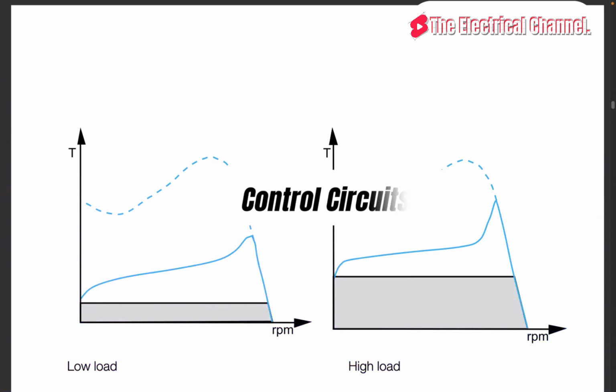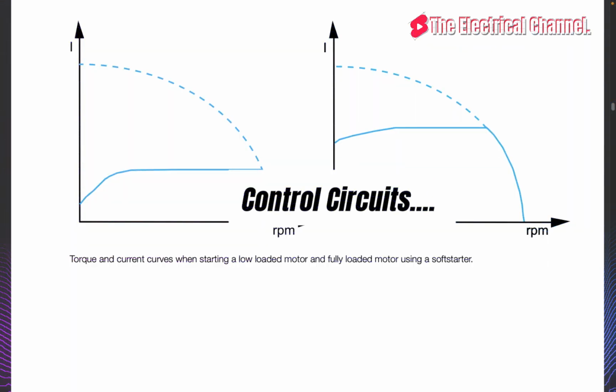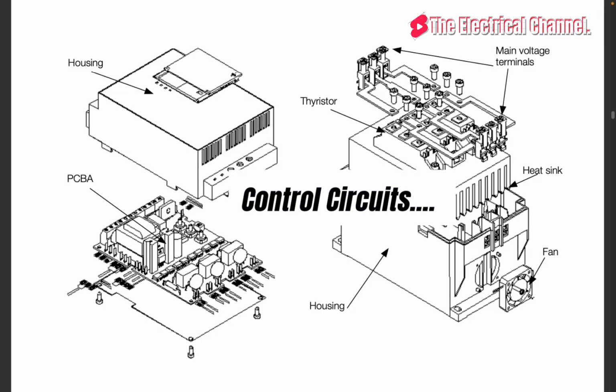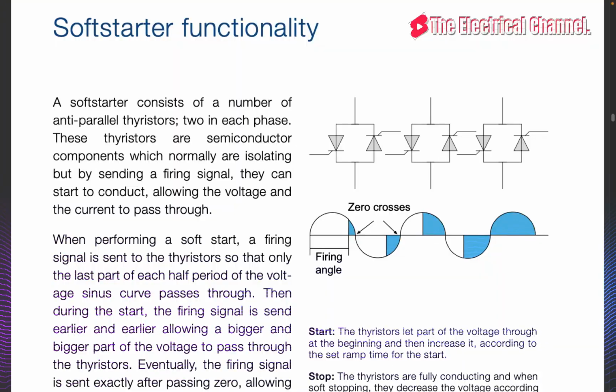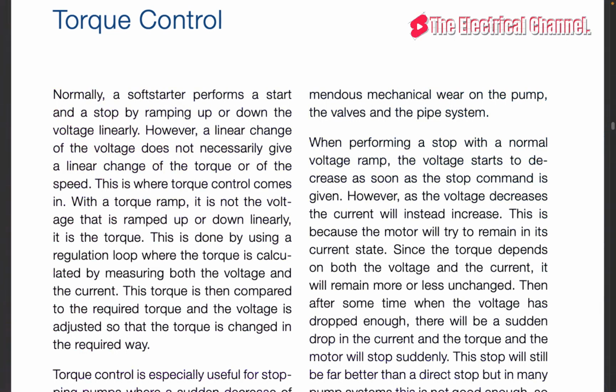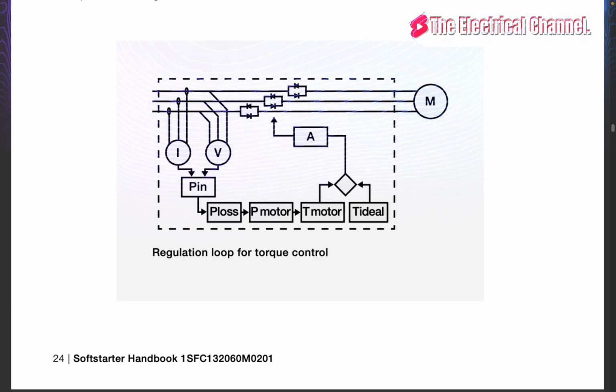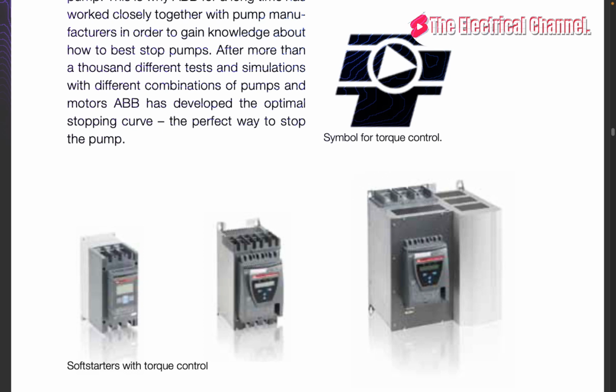Connection of control circuits to the soft starter. Control supply. The control supply voltage is the voltage supplied to the circuit board, fans, etc. in the soft starter. The terminals are usually marked 1 and 2. A common voltage is 100 through 250 AC volts.